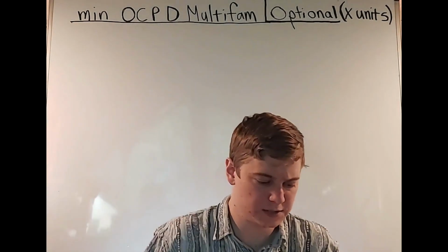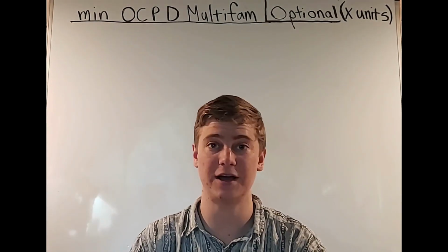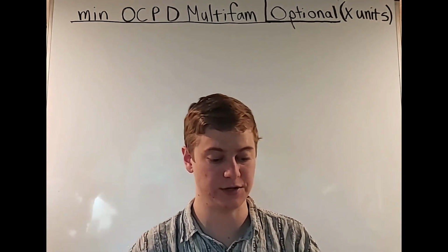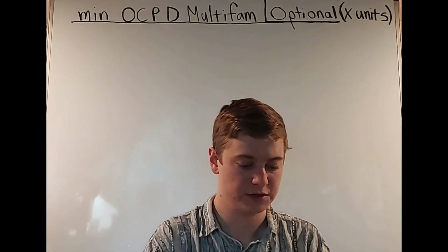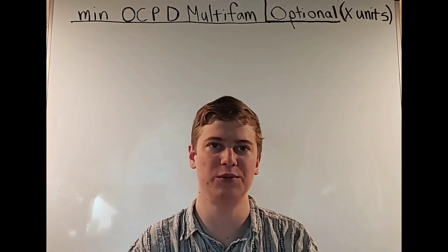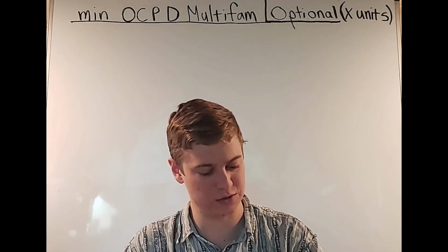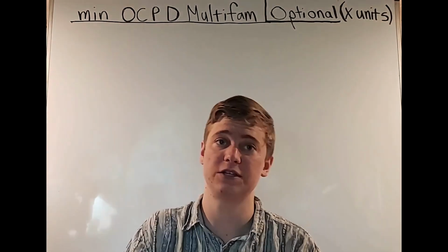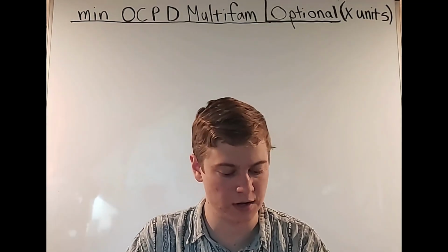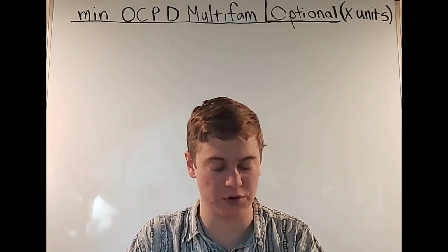Okay, we're going to go on to the next page. Again, we see article 220.84 dwelling unit. Here's where it tells us if we have 3 or more dwelling units, it is permissible to use table 220.84, and this is if all of the following conditions are met, where you see underneath it says 1, 2, and 3. And just like a lot of these rules in the load calculations, rule number 1 is the most important. No dwelling unit is supplied by more than one feeder.